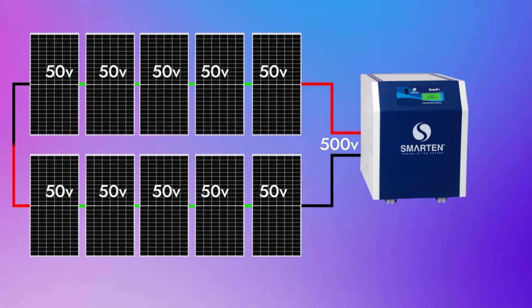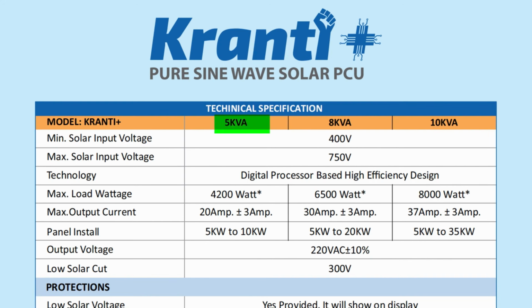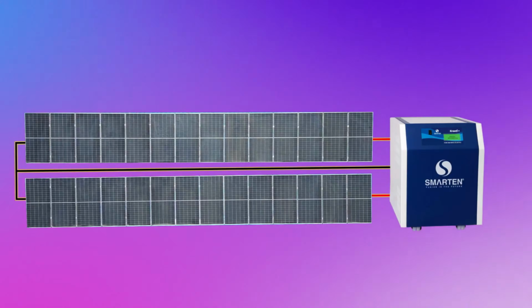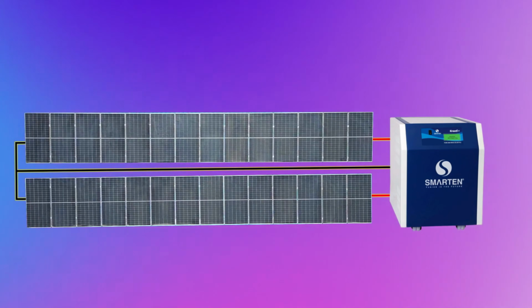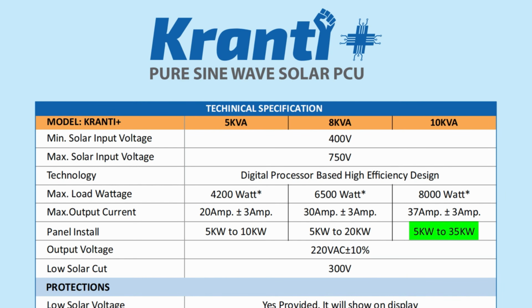You can increase the capacity depending on the inverter model. For example, the 5 kVA inverter can run up to 4200 watts of load, so installing 5 kilowatts of solar panels will be ideal. Similarly, the 8 kVA inverter can run up to 6500 watts of load and requires at least 8 kilowatts of solar panels. The 10 kVA inverter can run up to 8 kilowatts of load and requires at least 12 kilowatts of solar panels. These inverters support a maximum input voltage of 750 volts, meaning you can connect up to 15 panels in a single series string. If you want to connect more than 15 panels, you must make separate strings of 15 and connect them accordingly. With the 10 kVA inverter, you can connect up to 35 kilowatts of solar panels.